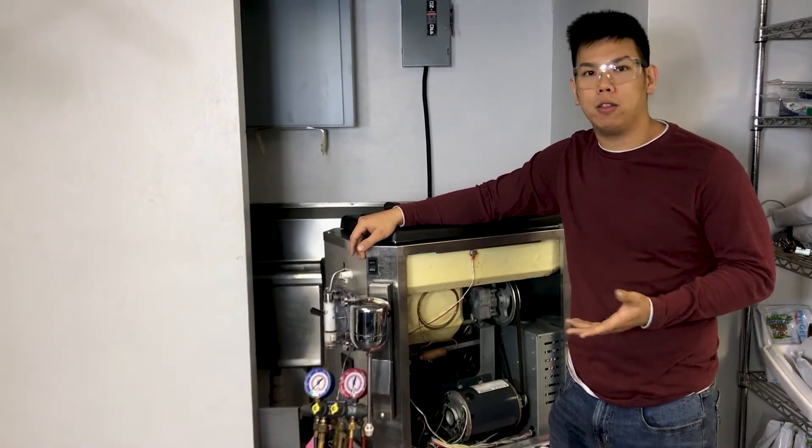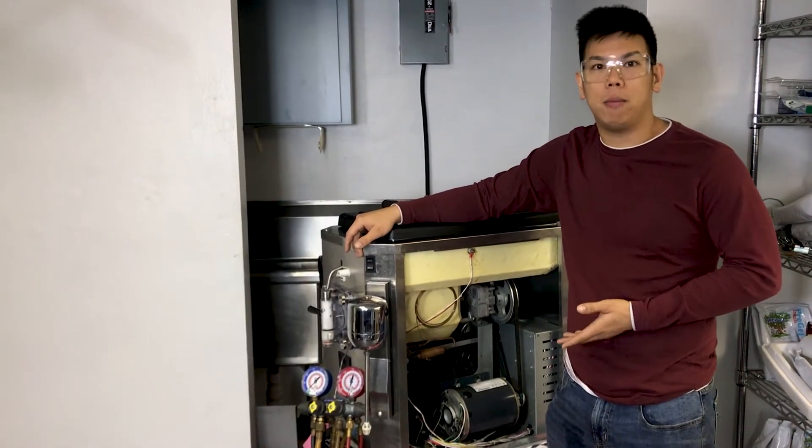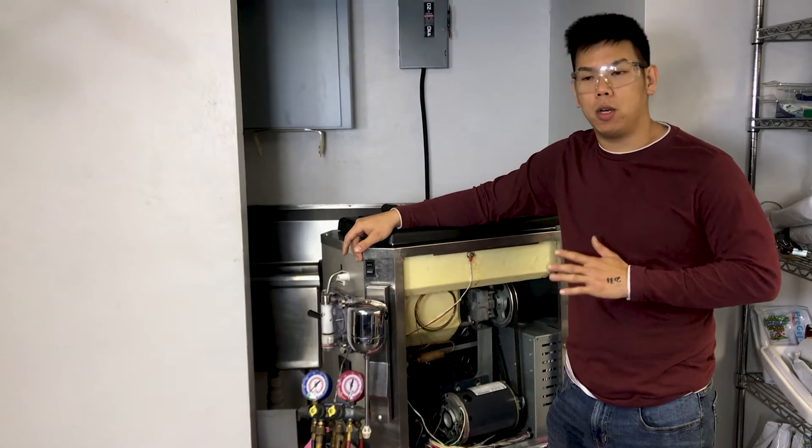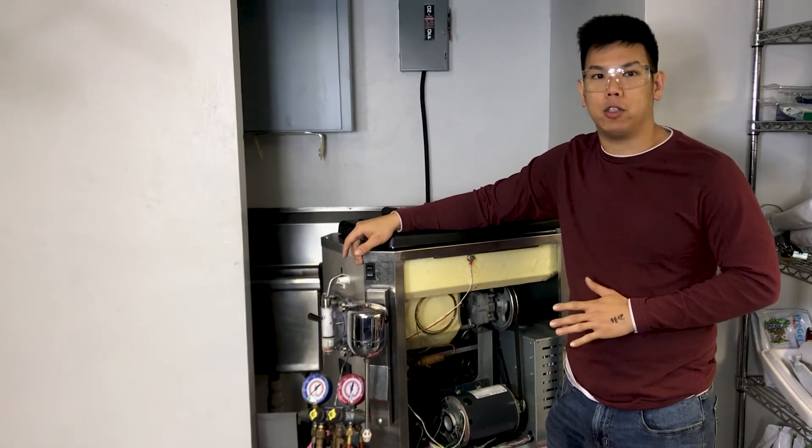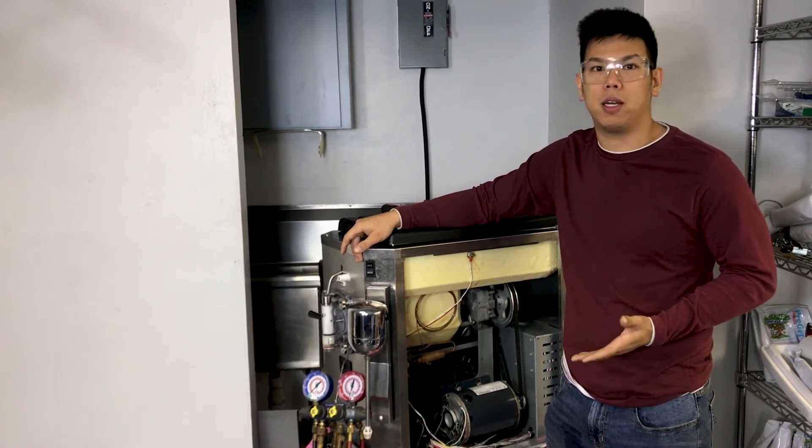A lot of times people go out and jump to a conclusion that the compressor is bad, but this is a quick way to ensure that you're running proper head pressures before you go out and drop some serious money on a compressor.